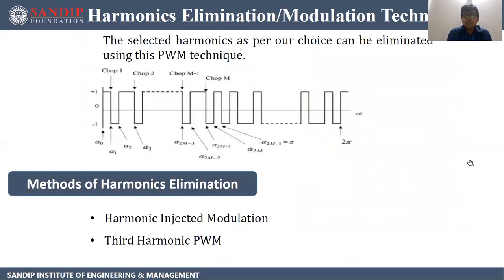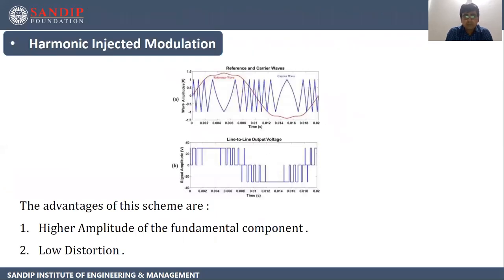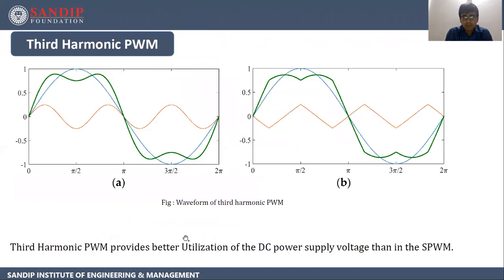Next is harmonic elimination or modulation techniques. Selected harmonics can be eliminated using PWM technique. The PWM signal has pulses of different widths. There are two main methods: harmonic injected modulation and third harmonic PWM. In harmonic injected modulation, a reference wave and a carrier signal produce the output voltage; advantages include higher amplitude of the fundamental component and lower load distortion. Third harmonic PWM provides better utilization of DC power supply voltage than SPWM.